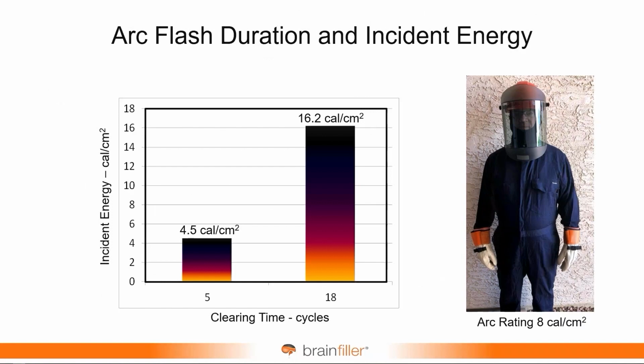Let's say that there is an arc flash study, and the calculated incident energy at a given location is the number on the left, 4.5 calories per square centimeter. Great. Okay, so there's a change. Somebody reruns the study and finds out instead of 4.5, it jumps to maybe 5.4 calories per square centimeter. So what? If you wear 8-calorie PPE, I wouldn't consider that the end of the world. 8 calorie per square centimeter PPE is still going to work. Now, the arc flash boundary may increase a little bit, and I'll show you how you can get around that.